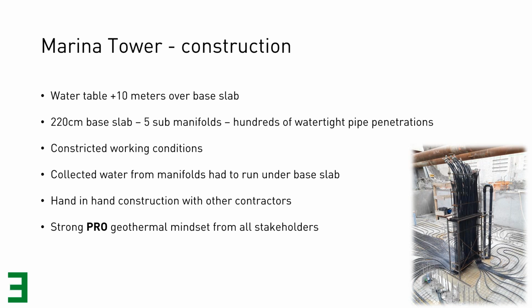We had a very constricted, confined working space, with many construction companies on site at the same time. The collected water from the manifolds had to run back into the slab. You can see the one pipe with a 150 diameter on the right-hand side—we had to collect the water on top and bring it back below the base slab, to the main manifold for the heat pumps, which we don't do very often, but there was no other way here.